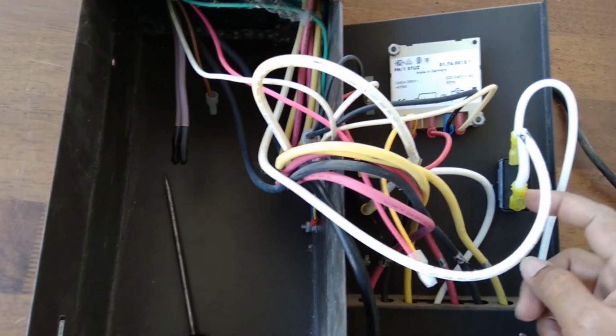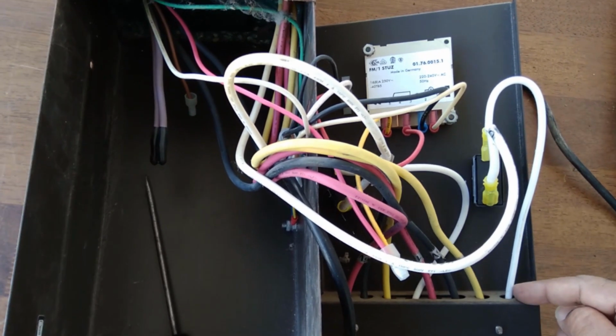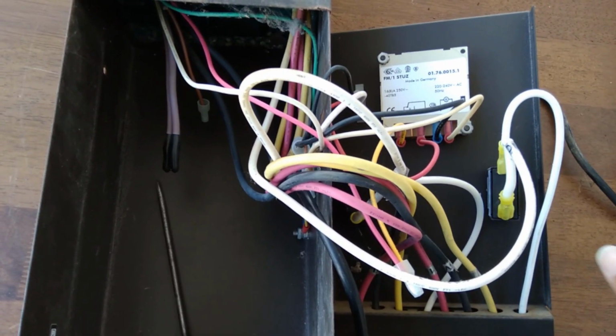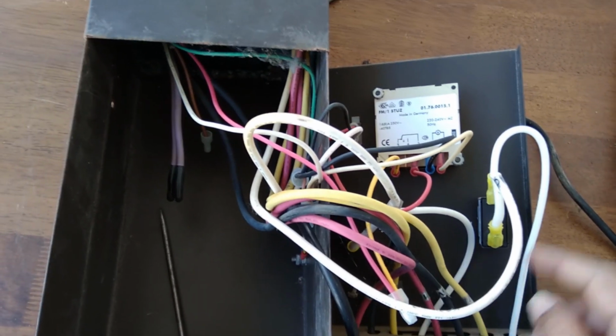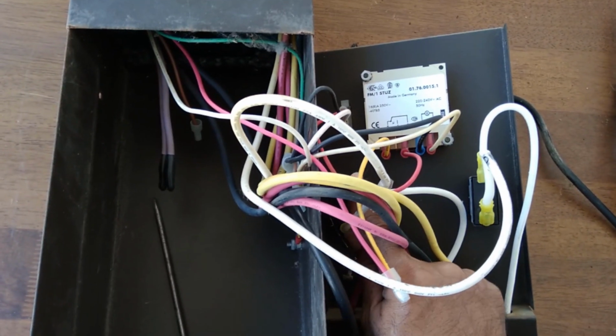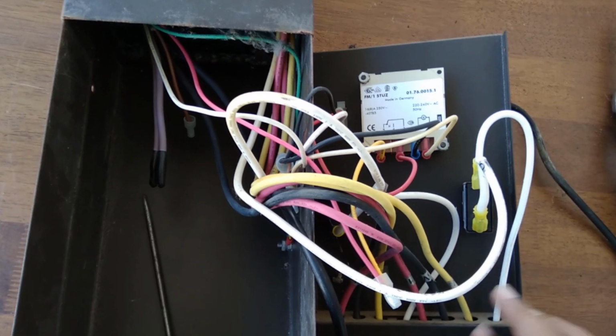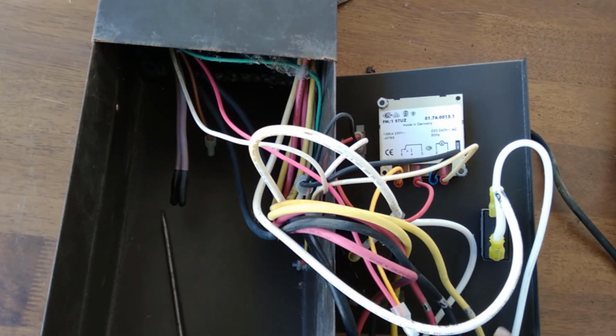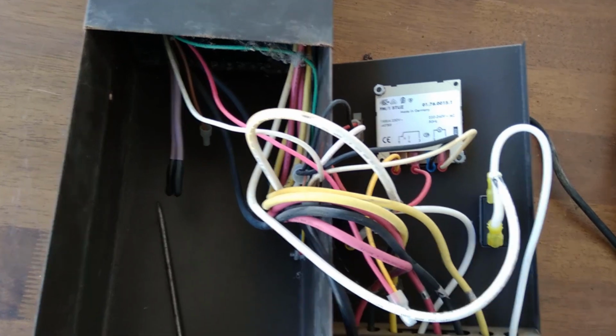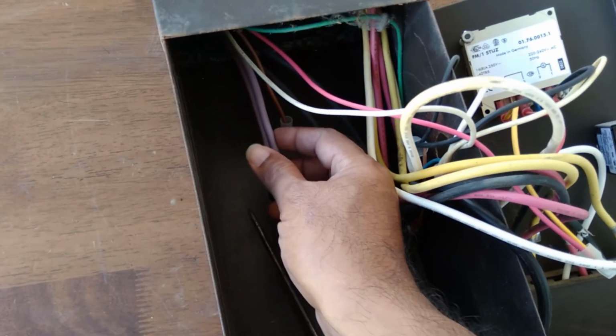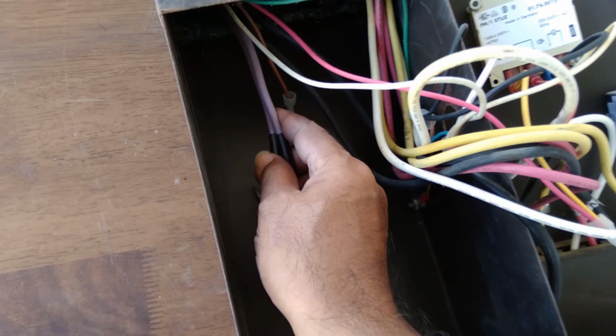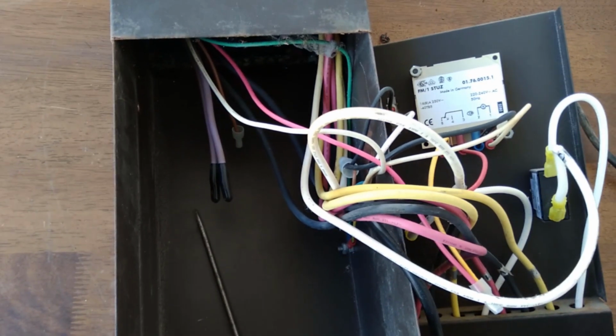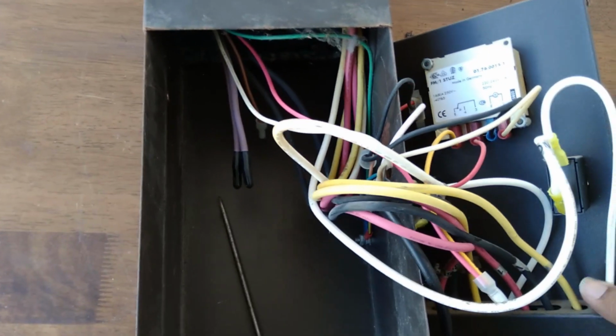Coming off the transformer, both are identical, so both feeds are identical. I assume they are not connected, and we'll test that. And this is our common. The switch is on the common. So the common is switched, again sensible, because each of these feeds are separate. And it's identical on the next side. So switched common, we have yellow for 12, we have the black for 13, we have the red for 15, and as I said, I assume this purple was a 14, which they have not used. They both are completely identical each side, and it's just a switch.